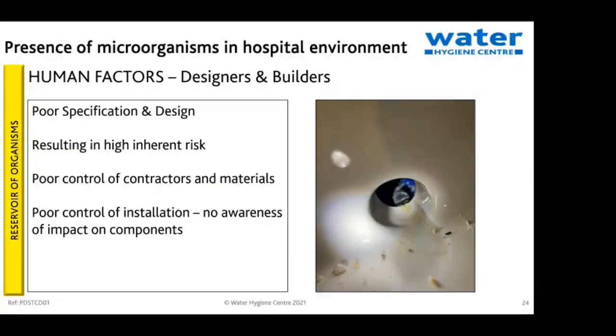Let's look at designers and builders. We can have poor specification design resulting in high inherent risk, poor control of contractors and installation, and no awareness of impact on components. These include clinical wash-hand basins used as urinals during construction, components not kept sealed and covered during installation, and domestic hot water returns not installed to the specified detail. A recent example of a new build with 150 outlets had none installed to the specified 300mm.